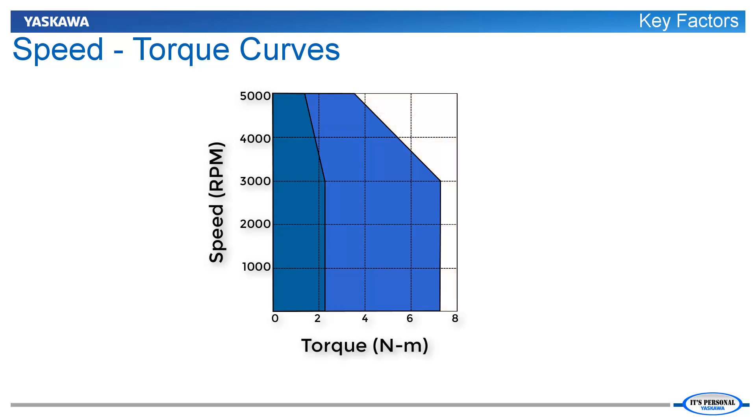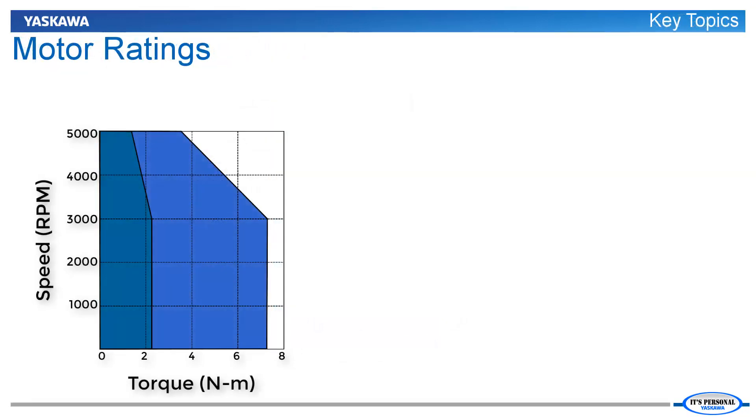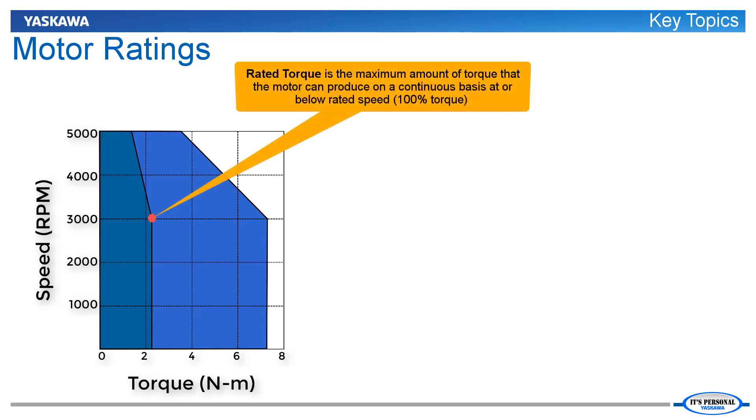When selecting a motor, it is imperative to ensure that the speed-torque curve is used effectively. The speed-torque curve displays several points of interest. Rated torque is the maximum torque the motor can produce continuously at rated speed and lower and is limited by motor heating. This rated torque is given the value of 100% torque.